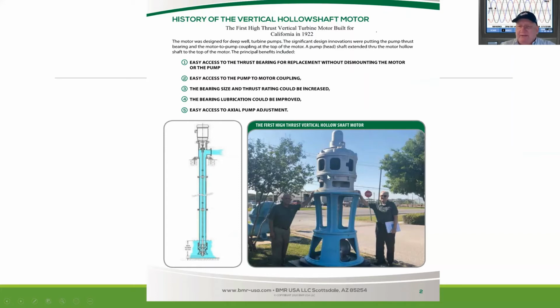I also strongly believe in this type of design, other than the verticals, which are the submersibles, where they take the motor winding and stick it down in the water right by the pump. Yes, it makes it easier to install, but it also cuts the size of pipe that is coming out. So, regarding the loss factor between a submersible pump and a turbine pump, these are harder to install, but they do last longer and they're much more efficient. Typically 10, as much as 15% more efficient, to have the vertical hollow shaft motor that goes on top of the regular turbine pump compared to the submersible.